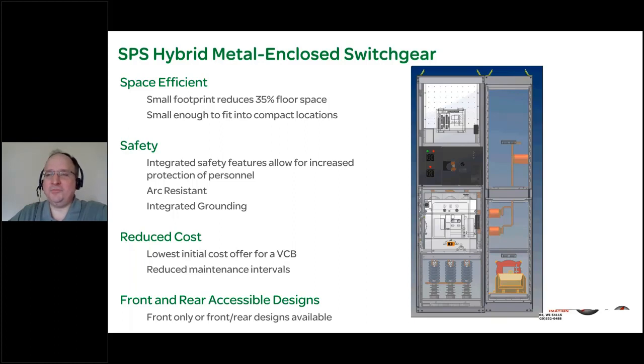And once you walk up to the switch, you open it, verify visible confirmation of blade disconnect, move the tool to a separate port on the front of the mechanism and ground it, and then verify through the front port that it's grounded. Apply your lock, so you've grounded and locked out and tagged out, and it's taken you 10 seconds, required no personal protective equipment, and is perfectly safe. Once you've experienced that versus the traditional method, you would never go back to the old school way of grounding.